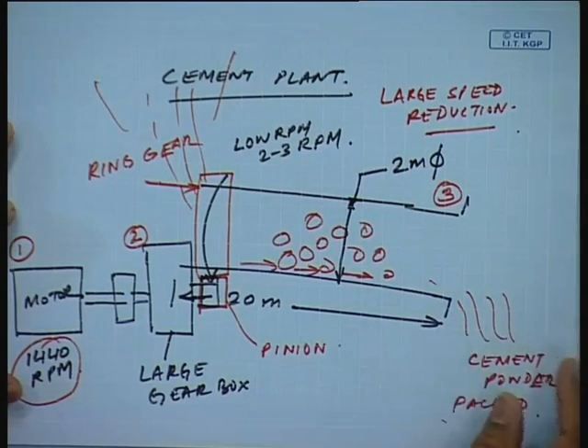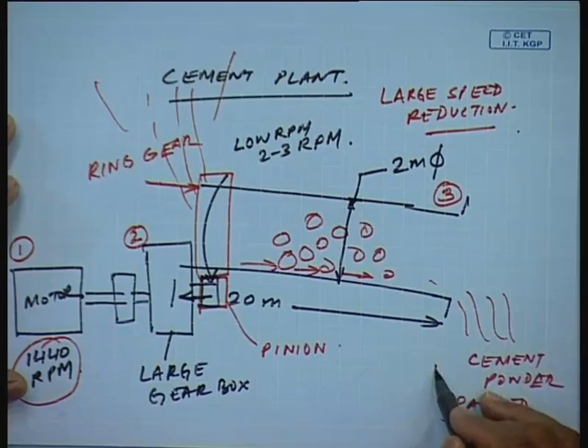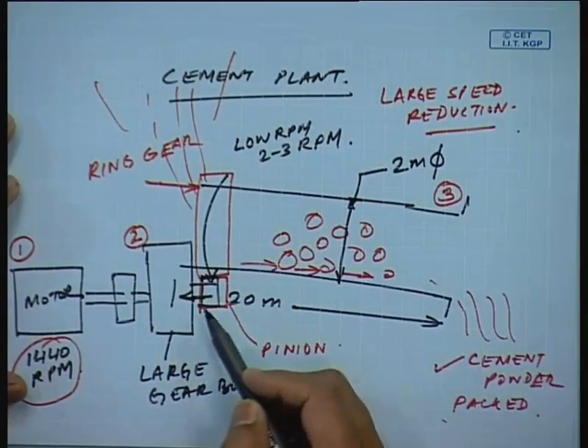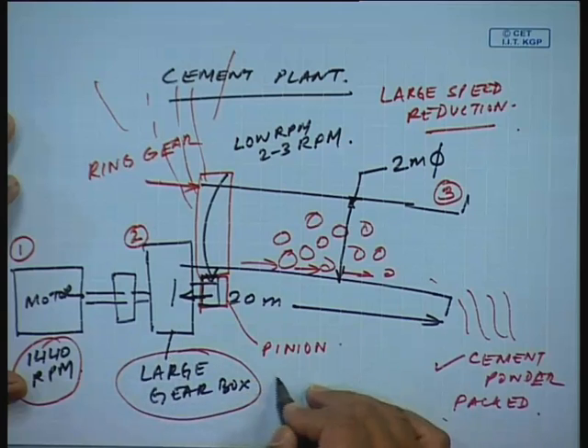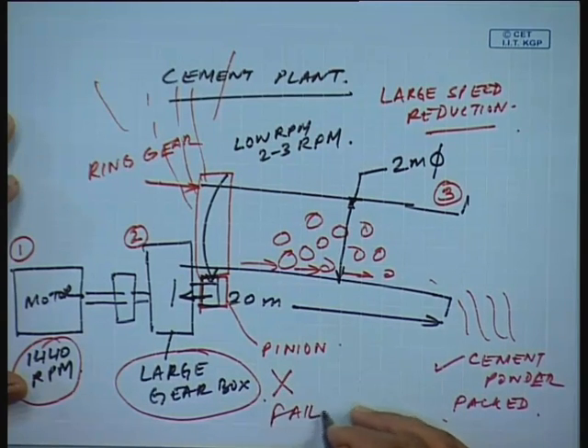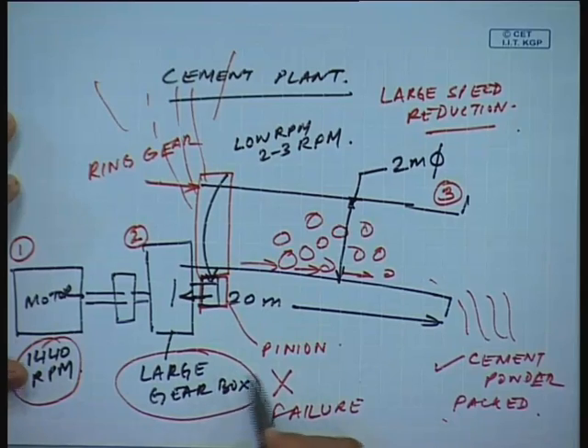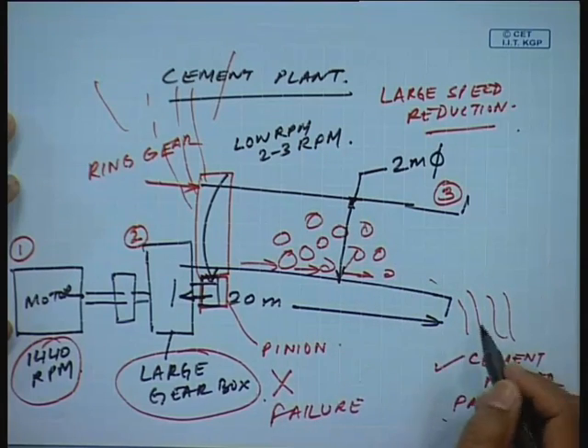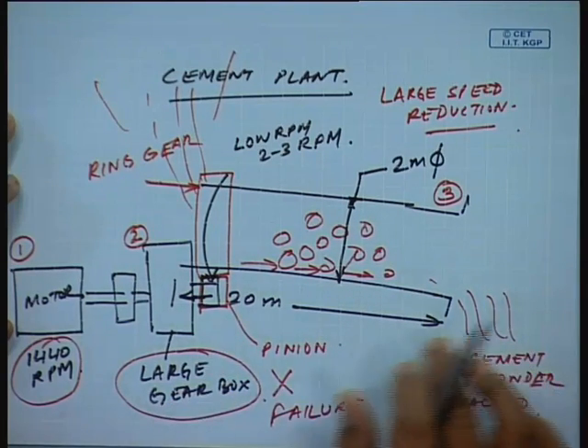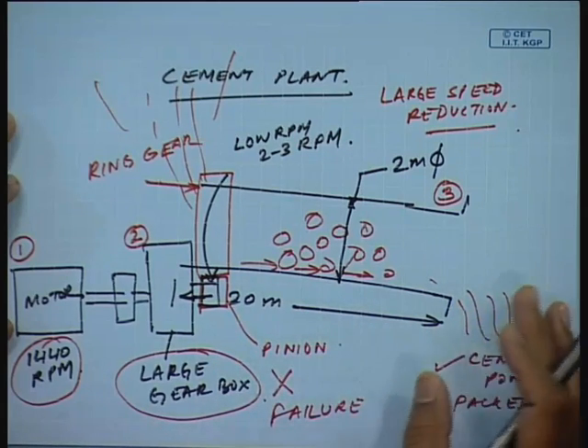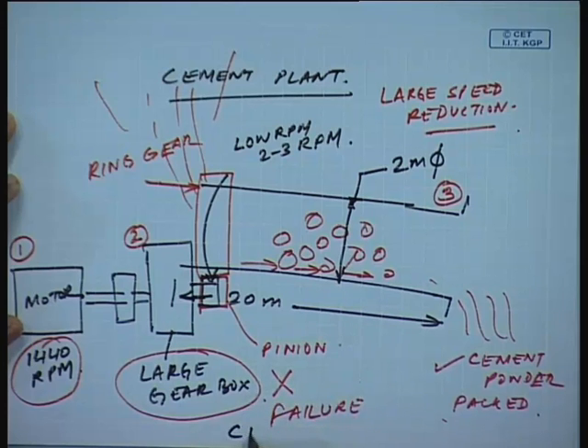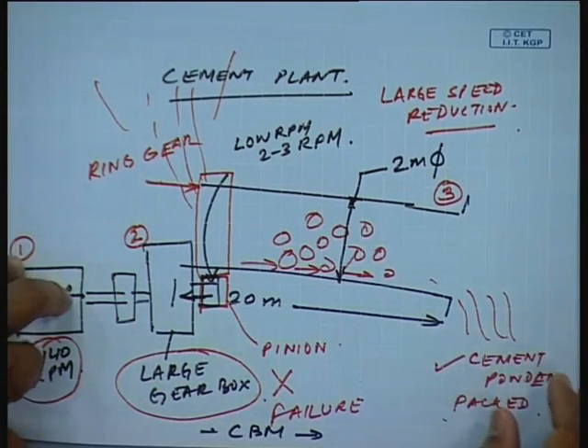If the gearbox fails for some reason — and this is a critical component — the mill is not going to rotate and there will be no cement. This is going to critically affect the process, output, and productivity of the plant. So I have to be very careful about the gearbox's maintenance and CBM must be done on this gearbox to evaluate it around the clock.